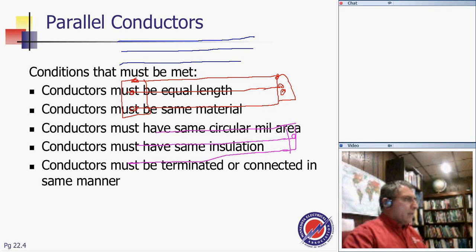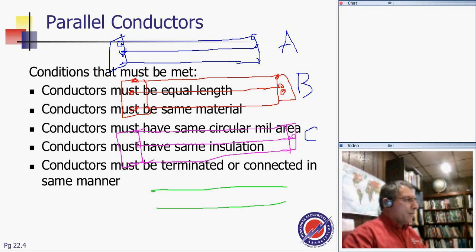Is my lug, and I'll draw this one in a second, and you can see how we parallel the conductors. So we just go back and tie these at the end here. That's what parallel conductors are all about, right? Tying at the end to the same lug. That's paralleling. Here's my phase A, here's my phase B, and here's my phase C conductors. And suppose I need a neutral, so I have to parallel my neutral: neutral 1, neutral 2, neutral 3. Tie them at the end, we'll lug a three-conductor lug, and off you go with a parallel system.